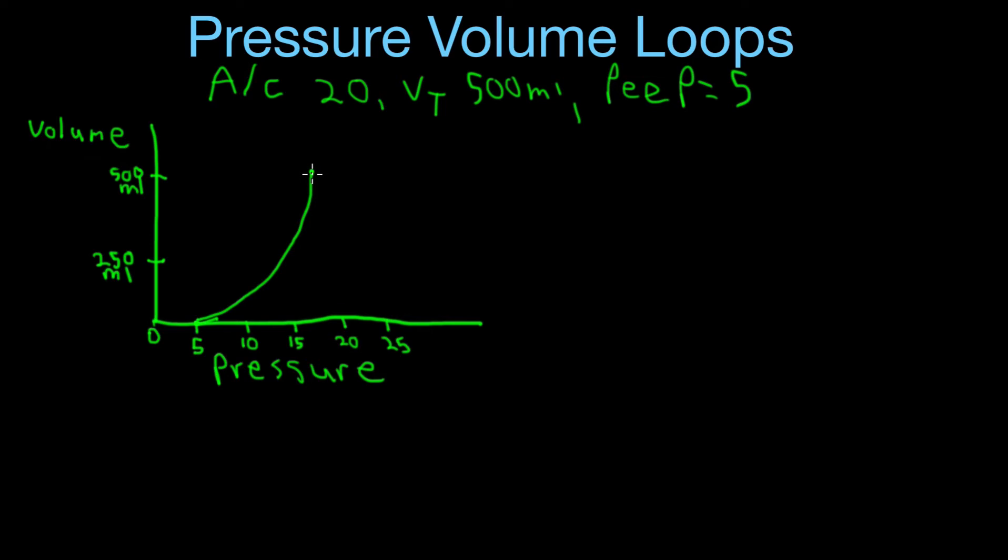Now once it reaches this point, it's going to cycle off and the patient is going to exhale, and then everything will start to decrease again back down to wherever the set PEEP level is, which is 5. Okay, so this is an example of a machine delivered tidal volume of 500 with a PEEP setting of 5.